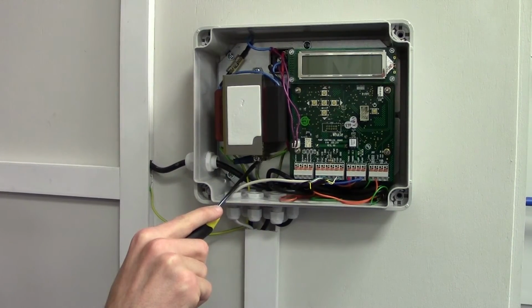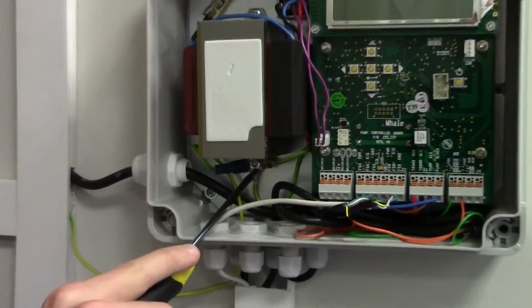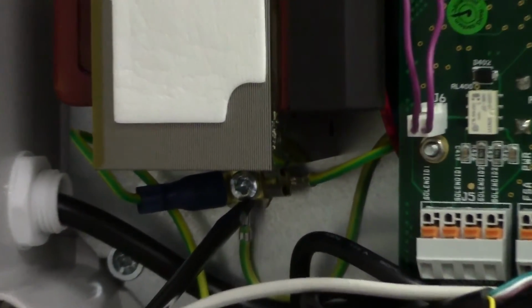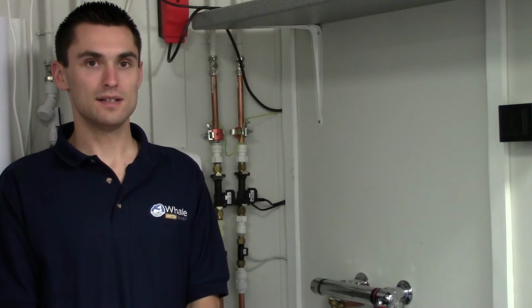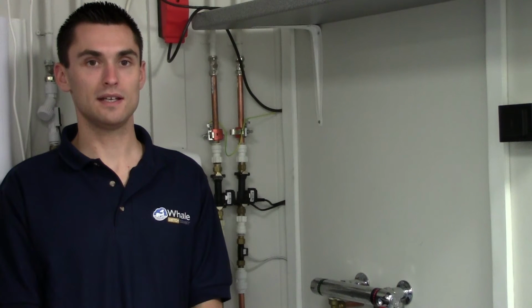The earth wire then runs to the earth clamp inside the control box and is connected using a crimp as can be seen here. When fitting the Venturi sensors, the signal wire must be no more than 5 meters long. The sensor cable must not run along any mains wiring and the sensor cable runs are to be kept as straight as possible, avoiding cable crossover as can be seen here.